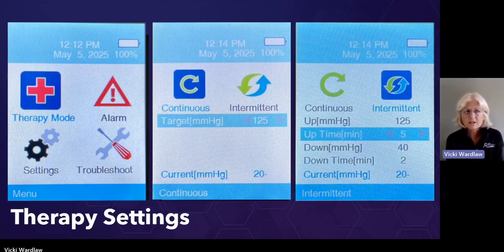If I wanted to change that, the target mmHg is highlighted. There is a left and right arrow, gray arrows on either side of the 125. That is where I would use my arrow to either increase or decrease my setting in increments of 5 millimeters of mercury. So if your provider is ordering 130, for instance, you would use your right arrow, press that once, then that target millimeters of mercury would change to 130.